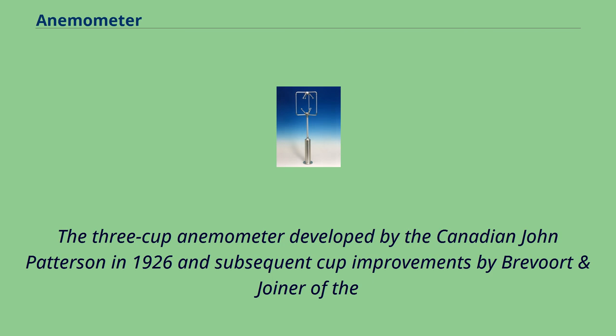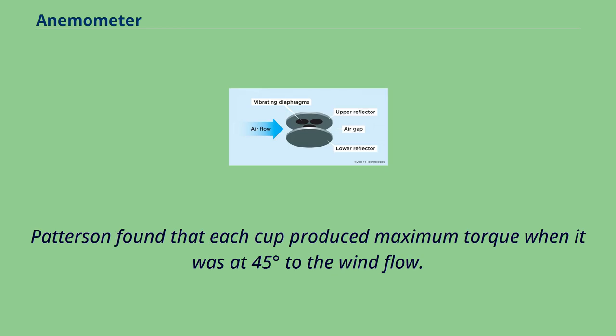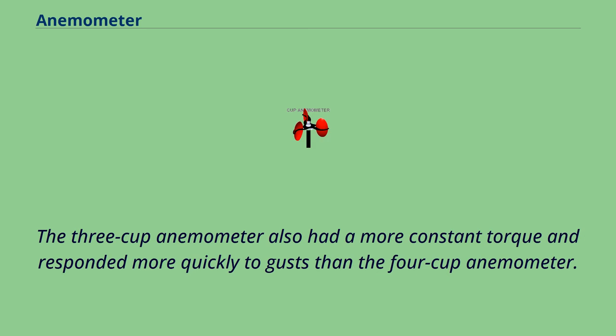The three-cup anemometer developed by Canadian John Patterson in 1926 and subsequent cup improvements by Brevoort and Joyner of the United States in 1935 led to a cup wheel design with a nearly linear response and had an error of less than 3% up to 60 mph. Patterson found that each cup produced maximum torque when it was at 45 degrees to the wind flow. The three-cup anemometer also had a more constant torque and responded more quickly to gusts than the four-cup anemometer.